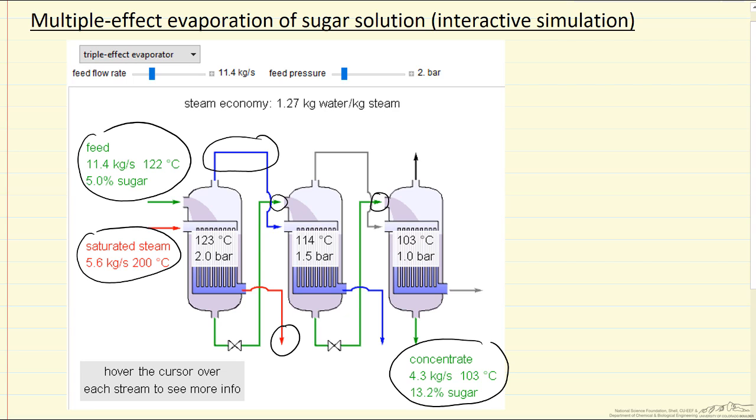The significant advantage is instead of using additional outside steam, we use the evaporated water in the second stage. For this to work with a temperature difference, we run the second effect at lower pressure and lower boiling temperature. The third stage follows the same pattern - steam from the second stage enters the third stage at lower pressure and temperature, maintaining a temperature difference for heat transfer.